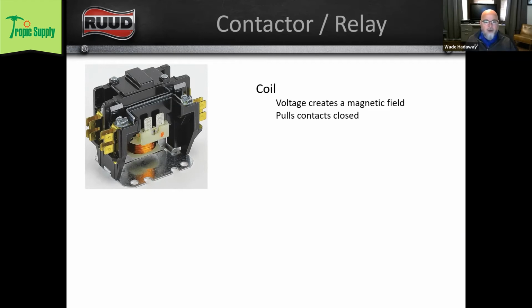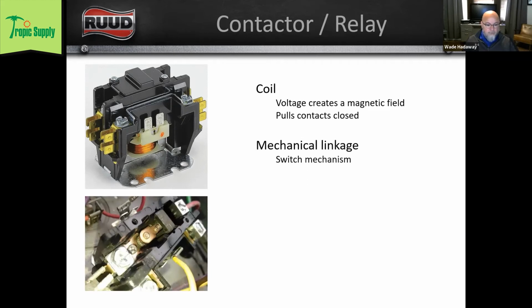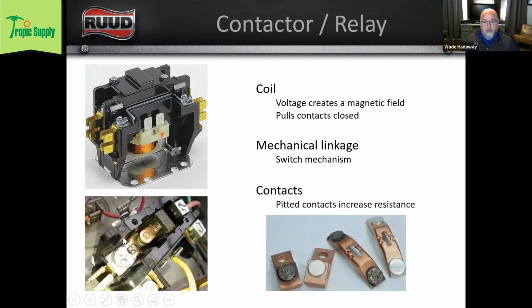So you can see sort of at the bottom, the coil is really just that. It's a coil of copper wire. And when we send our control voltage through that copper wire, it creates a magnetic field that pulls this set of contacts closed. And in the off cycle, when we de-energize our coil, you can see right here, there's a spring at the top of this linkage, and this spring pulls the contacts back up. So we create a magnetic field by sending 24 volts through this coil. It turns it into an electromagnet, and that pulls this set of contacts closed. You can see here that the contacts are actually what opens and closes on the switch. And when the contacts are closed, that completes our circuit and allows power to pass through it.